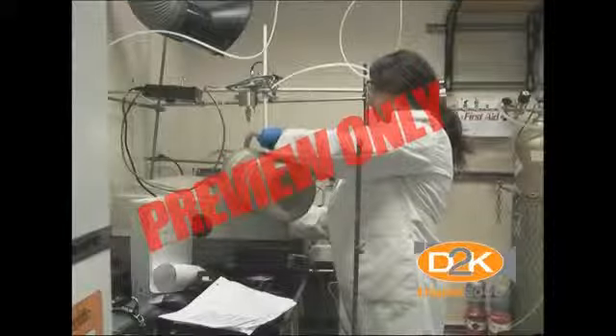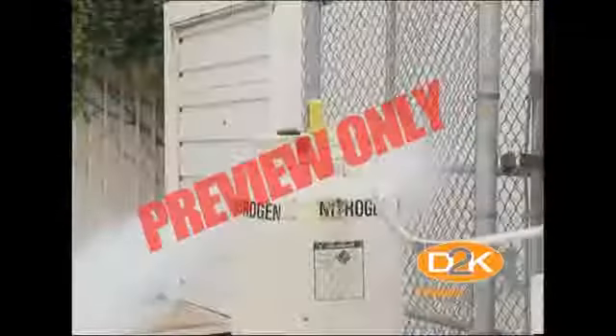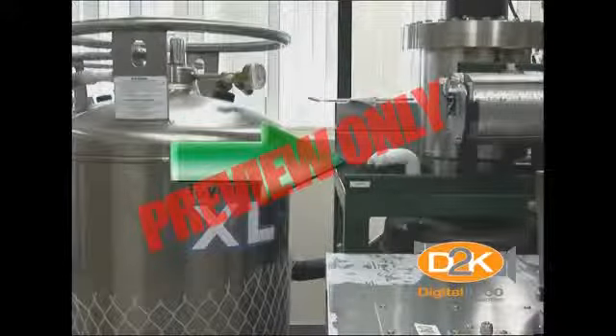Transfer of cryogenic liquids must be conducted slowly to minimize boiling and splashing of the cryogenic fluid. Transfer of cryogenic fluids from open containers must occur below chest level of the person pouring liquid. Transfer of cryogenic liquids shall be conducted only in well-ventilated areas to prevent possible gas or vapor accumulation. All cryogenic systems must be equipped with pressure relief devices to prevent pressure buildup. Never refill dewars or transfer cryogenic liquids when working alone.